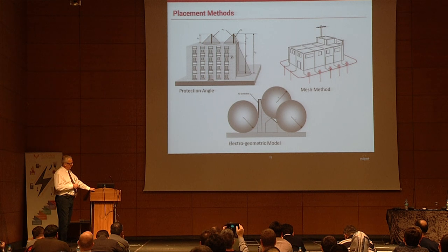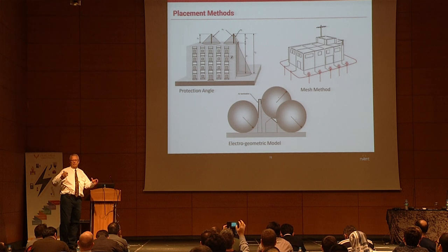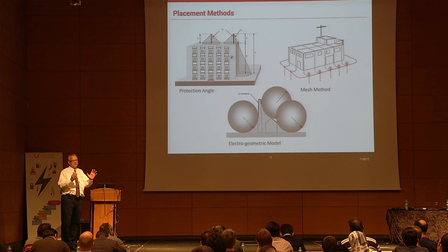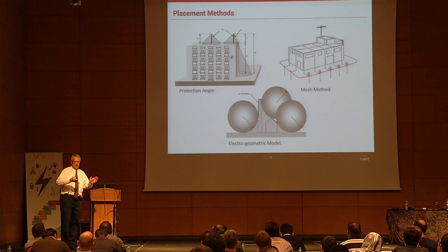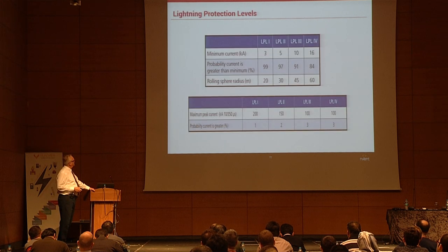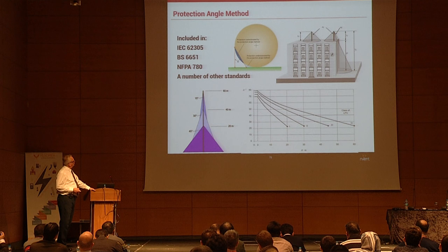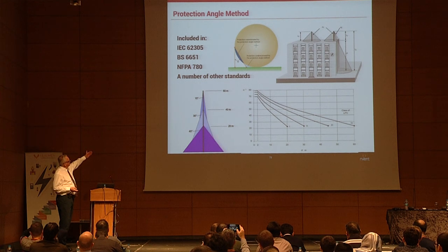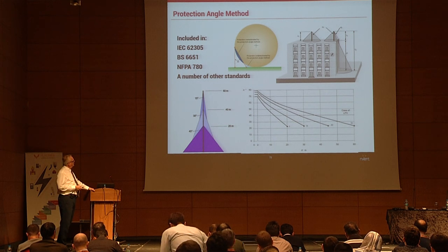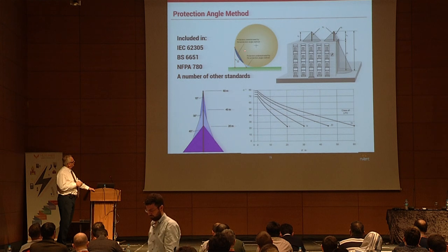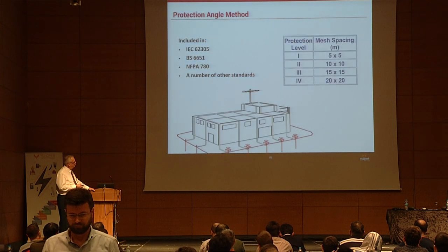The rolling sphere — electrogeometric model — rolls over the structure with a radius based on protection level, for example 20 meters for 99% protection, and where it touches is where you place your terminals. The rolling sphere is actually more conservative than the protection angle method, which might deem an area protected when the rolling sphere shows it is not. The protection angle is used in IEC, British standard, and NFPA 780 standards.